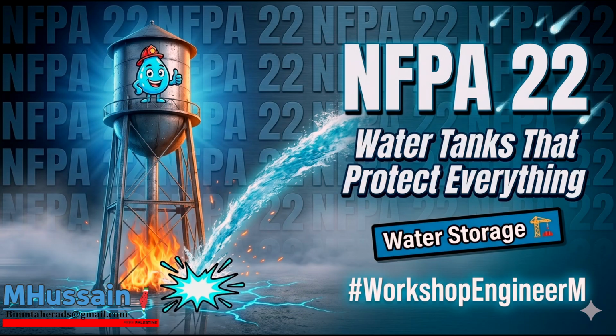So what is the solution? If the math requires 200 psi, but the valves can only handle 175 psi, how do you resolve that as the designer? You're forced to manipulate the volume variable in Boyle's law. The standard dictates that the engineer must select a physically larger tank. Oh, I see. A larger overall tank, holding the exact same amount of water, means you have a much larger volume of compressed air. And because you have more air volume, it doesn't have to expand as much to push the water out. Exactly. Therefore, you can start at a much lower initial pressure to achieve the exact same final expulsion force.